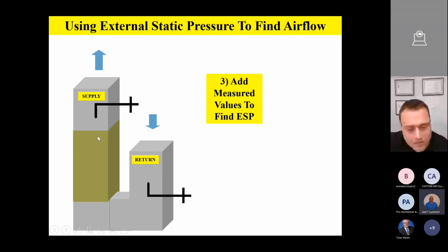And then because an air handler has a coil and a fan built in, we're always going to put our static pressure probe right in the supply duct, right in the supply plenum, and poke a hole and have it pointing right into the airstream as it comes off the air handler. Good questions. Any other good questions or comments? Everybody good? Excellent. Yes, please keep those good questions coming.